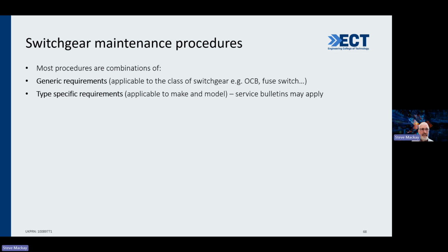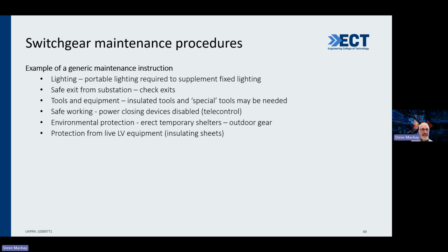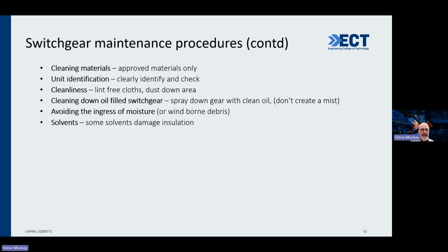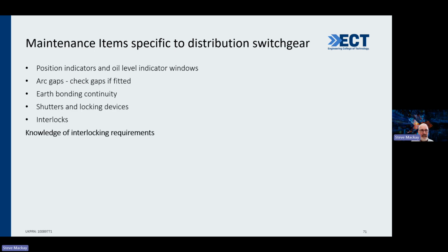So maintenance procedures. Most procedures are combinations of the manufacturer's requirements, service bulletins, and the class of the switchgear. So for switchgear maintenance procedures, you can see portable lighting required to supplement fixed lighting, safe exit from substation, tools and equipment, safe working, environmental protection, protection from live LV equipment. It's obviously all important issues. Cleaning materials, unit identification, cleanliness, cleaning down of oil-filled switchgear, spray down, avoiding ingress of moisture or windborne dust if you're out in the desert, and solvents can also damage your insulation. So be very aware of them.